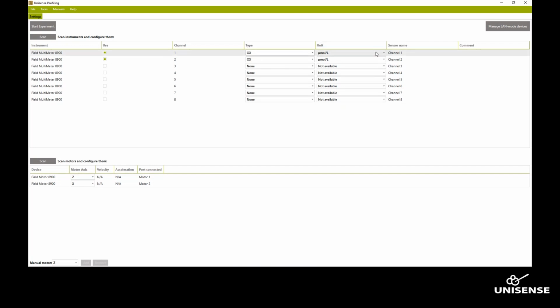You can choose what unit you want to work in. The default unit is micromoles per liter, and that is needed if you want to use the analysis part of the software. That will only work with micromoles per liter, not the other ones. But you can, if you want, work with percent saturation, milligrams per liter, nanomoles per liter, millimeter mercury, Pascal, or arbitrary units.